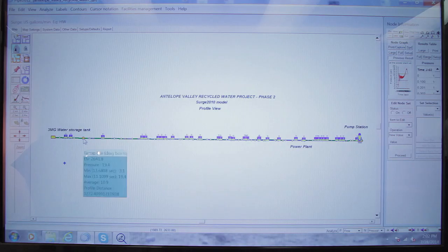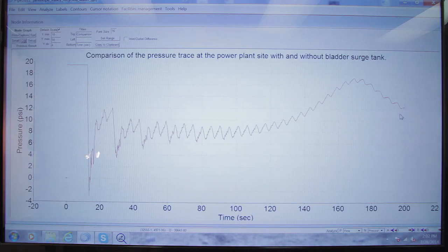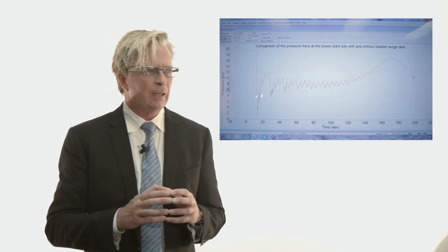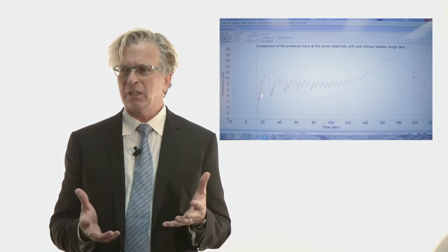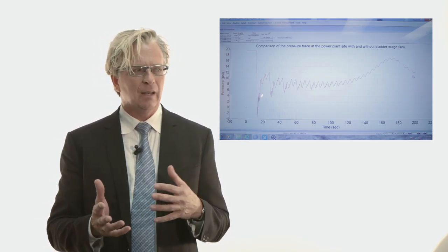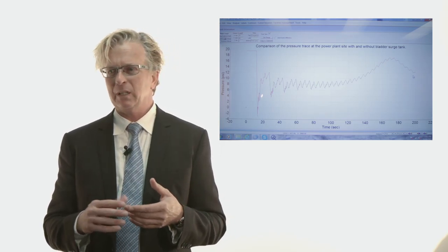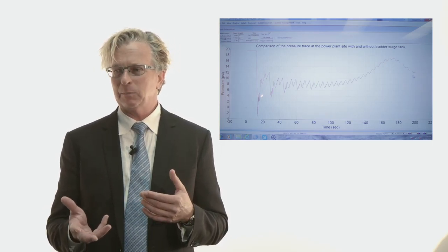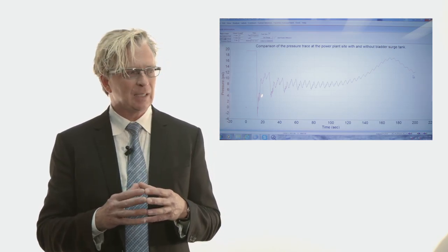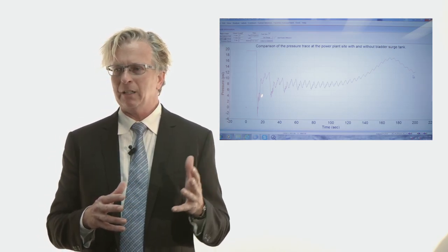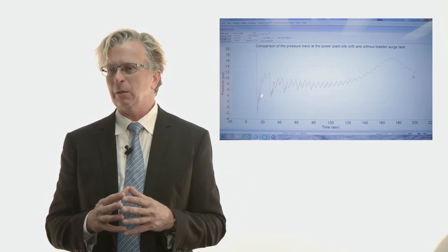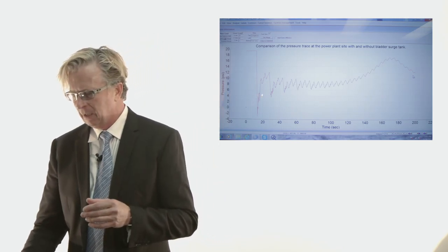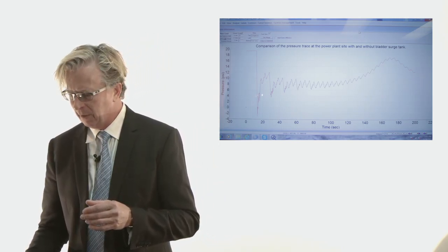Looking at that particular node at the end of the pipeline, in this case we're dropping to minus 3 psi. At this point, you look at the negative pressure rating of the pipe. Our rule of thumb for ductile iron pipe — we can accept up to minus 6 psi, never below minus 6 psi. PVC pipe is minus 2 psi. So at this point, you're looking at a lot more stress in the piping system, vacuum condition, and further evaluation of your air vacuum valve.